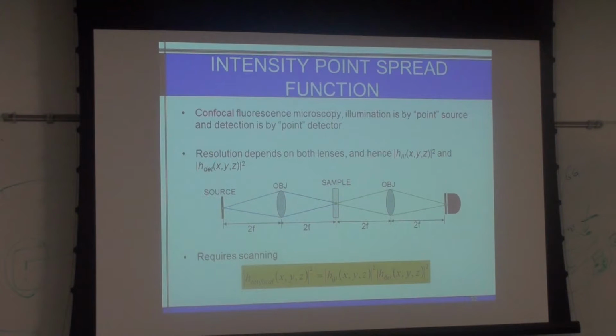When Minsky came up with this, you didn't have the computational power to really do the stitching of all the images together point by point. So the confocal intensity PSF is going to be what dictates the resolution on both ends: the resolution of this front optical system, what we call the illumination PSF, as well as the resolution of this back optical system, what we call the detection PSF.